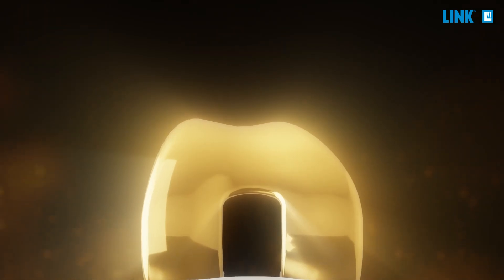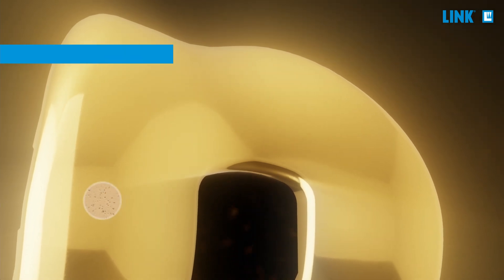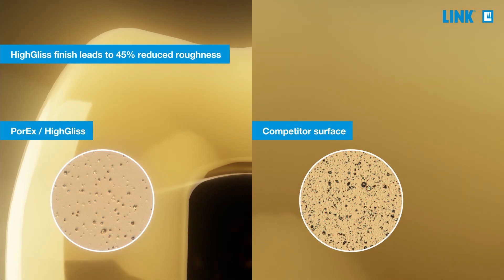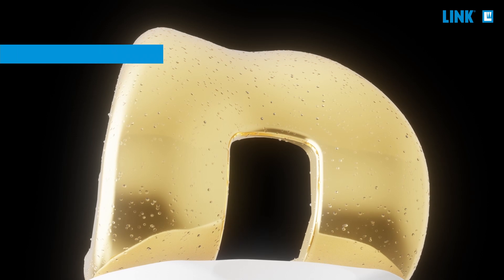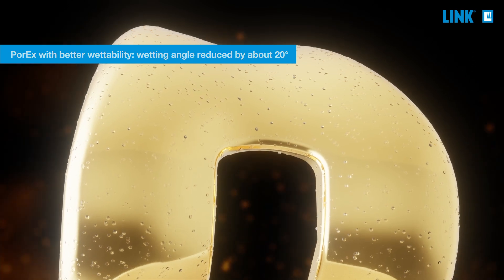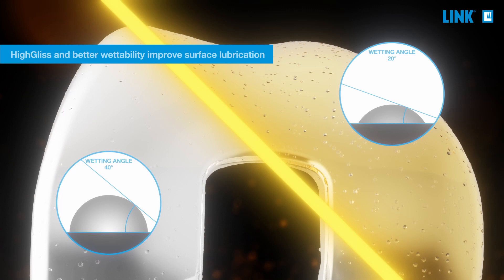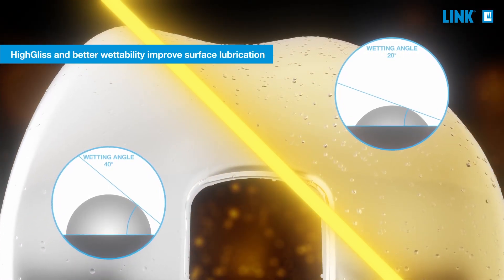PorEx shows excellent tribological behavior due to a proprietary HighGliss surface finish that reduces roughness by up to 45% when compared to competitor coatings. The ceramic-like surface of PorEx improves the wetting angle, and therefore increases wettability and lubrication when compared to uncoated implant surfaces. HighGliss and optimal wettability result in less wear.